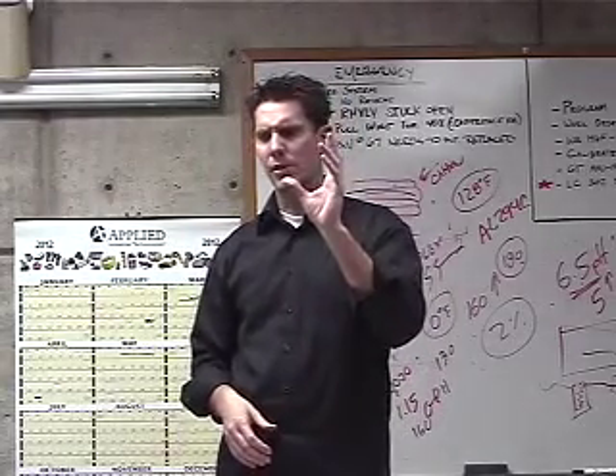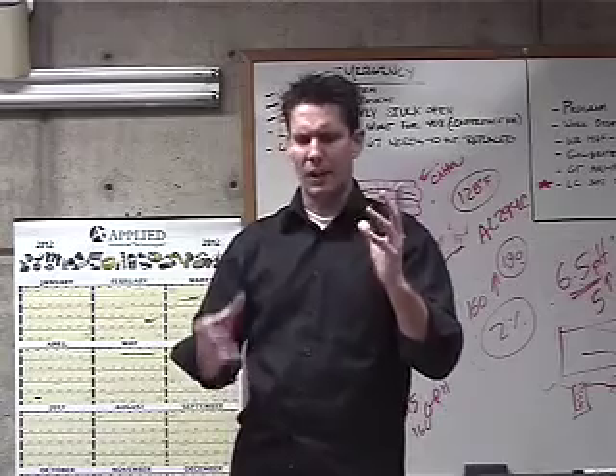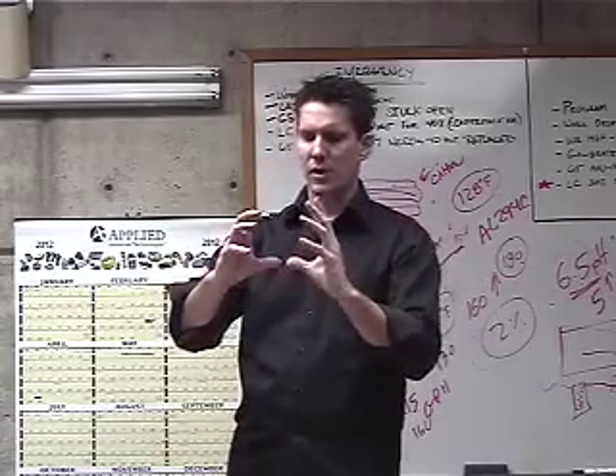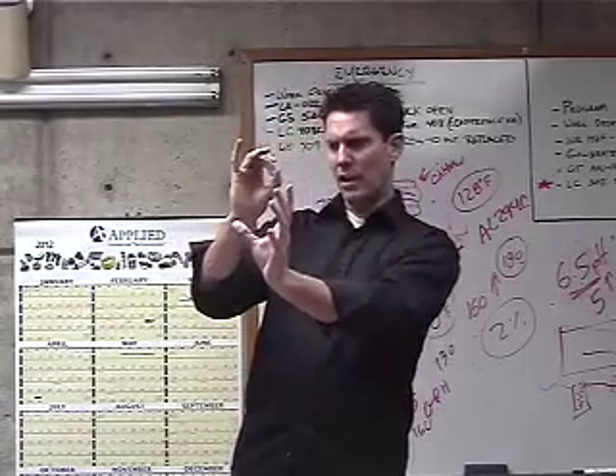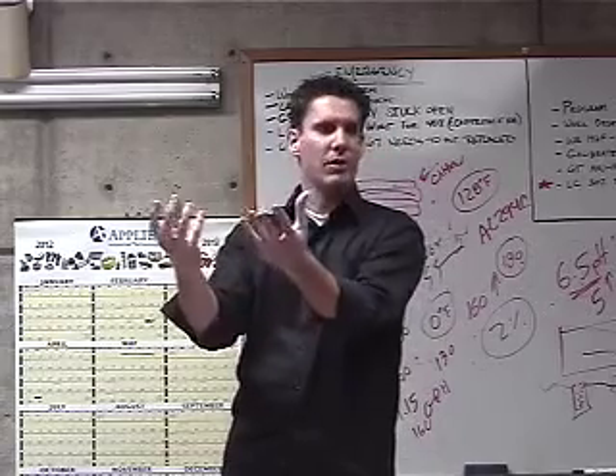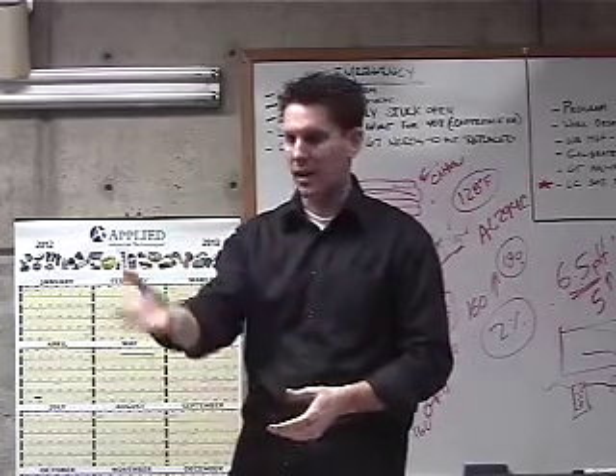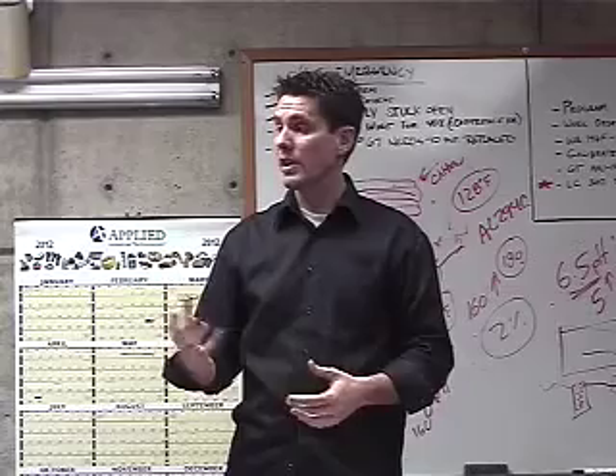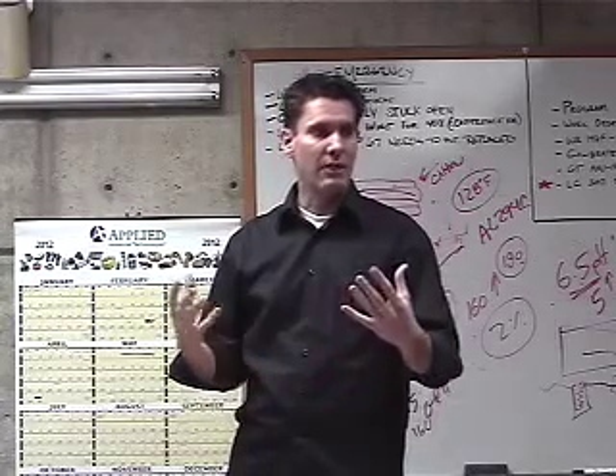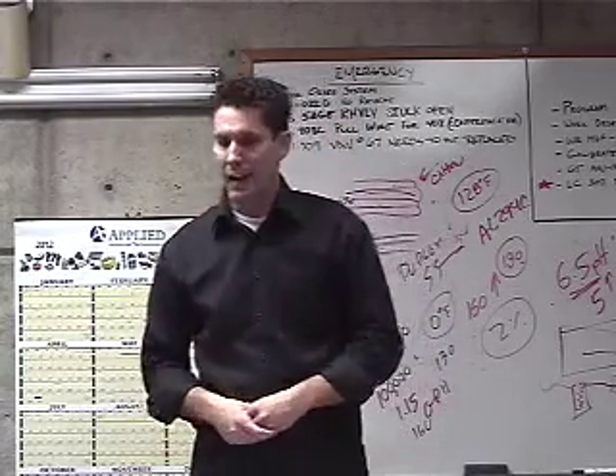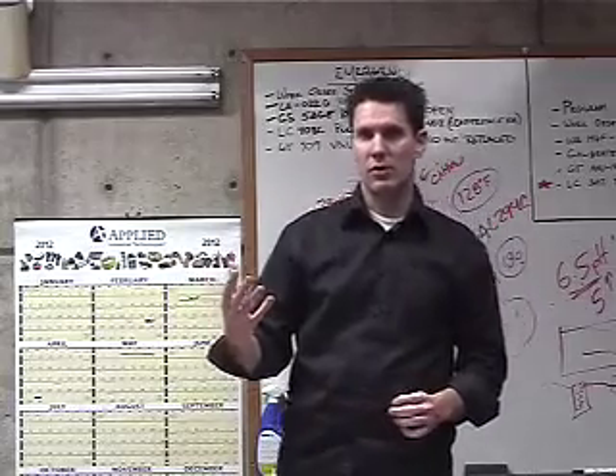On a lot of burners, not this one, but maybe on some of your other boilers, you can see soot when you look down the viewport, and you'll see glowing embers inside. Glowing embers, just like in a fire, it's the soot buildup. Soot is unused carbon. Okay, there's not enough oxygen to burn up all that carbon. You'll start to run smoky.